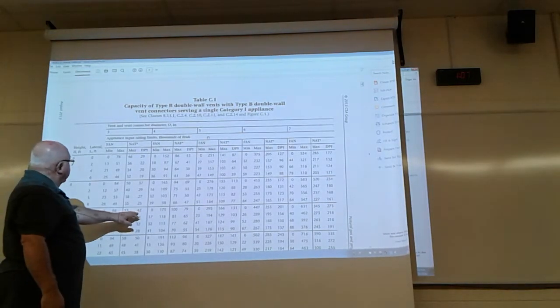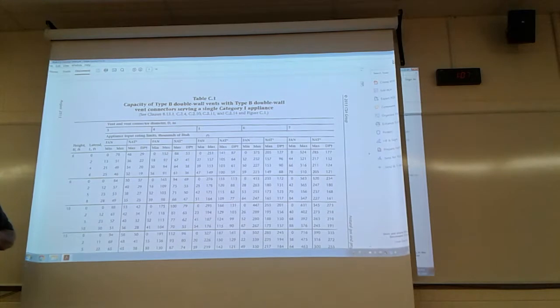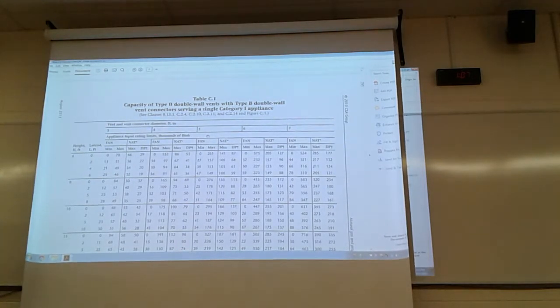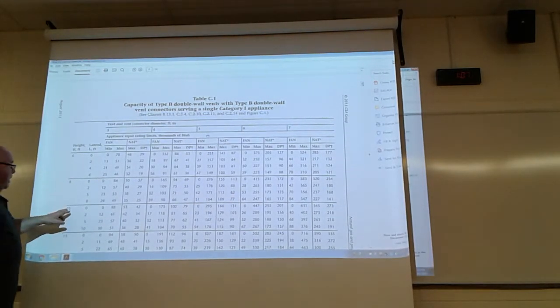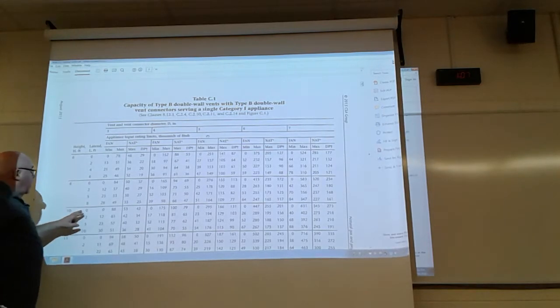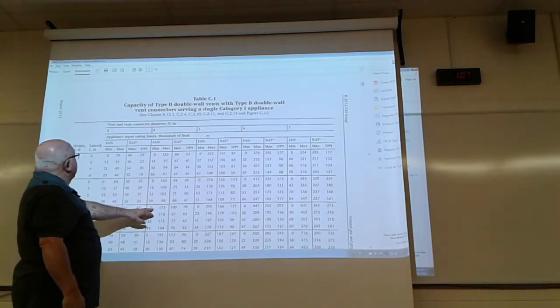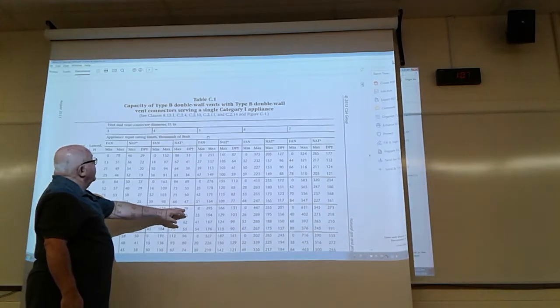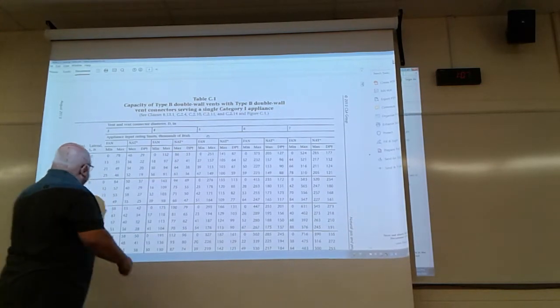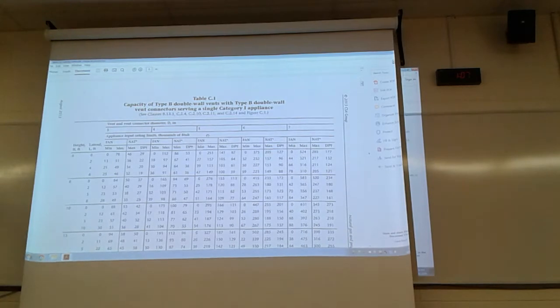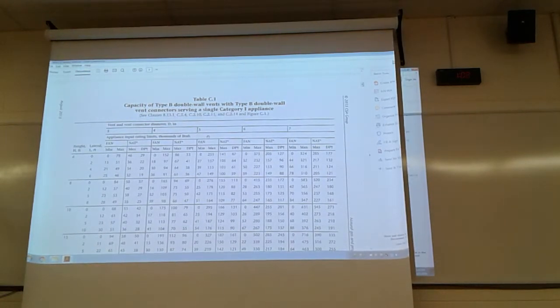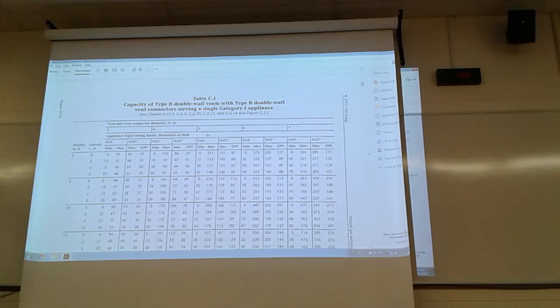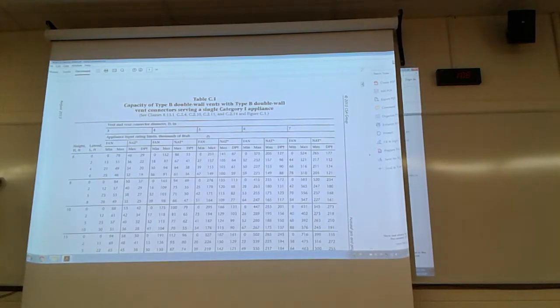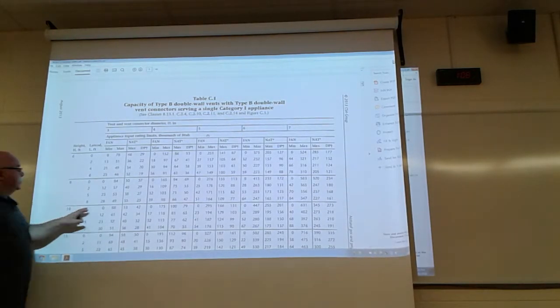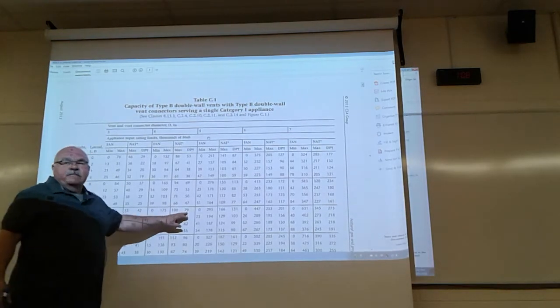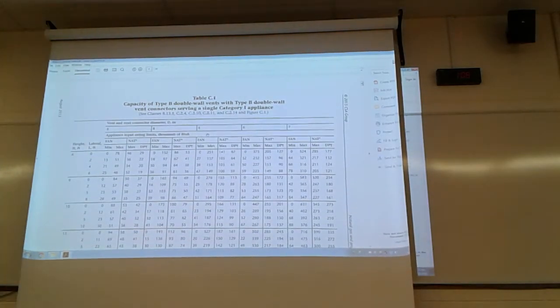You don't go up to 15? For gas, you go down, for oil, you go up. Worst case scenario. It shouldn't really make much of a difference, but anyways, we're going across, and we've got 4 inches of vent, and we've got 79. So 4 and 79. So a 4-inch vent, and it can handle 79,000 BTUs. Everybody good?